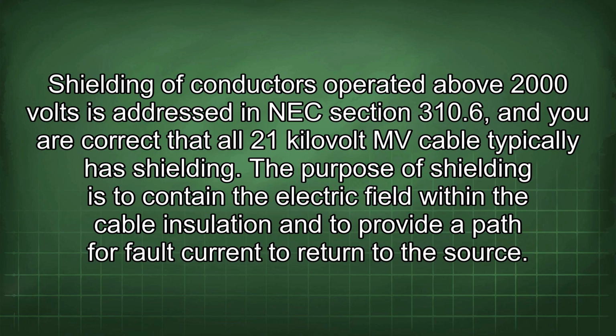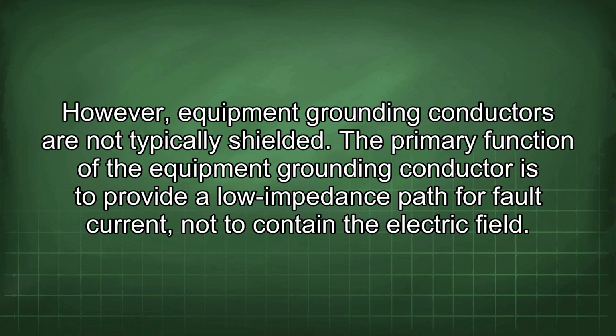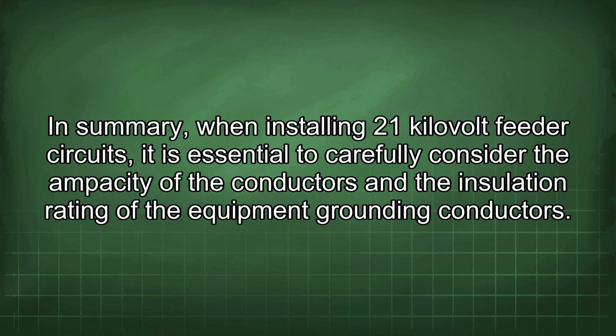Shielding of conductors operated above 2000 volts is addressed in NEC section 310.6, and you are correct that all 21 kilovolt MV cable typically has shielding. The purpose of shielding is to contain the electric field within the cable insulation and to provide a path for fault current to return to the source. However, equipment grounding conductors are not typically shielded. The primary function of the equipment grounding conductor is to provide a low impedance path for fault current, not to contain the electric field.